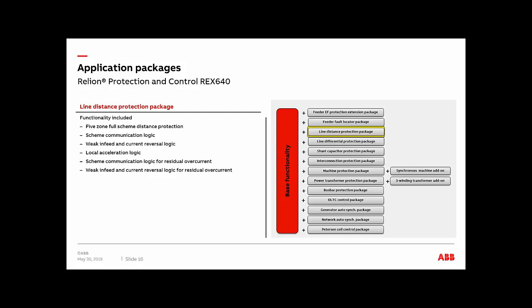There is also a functionality called weak infeed and current reversal logic, and pretty much it's used when you require additional logic to your traditional permissive transfer trips or POTT, PUTT schemes. You can add on logic with your weak infeed or current reversal logic, and this is mainly used when you're going to have parallel feeders. When the schemes can cause some kind of false trips, you can always have support and additional security from the logic provided by the relay, by the weak infeed and current reversal logic.